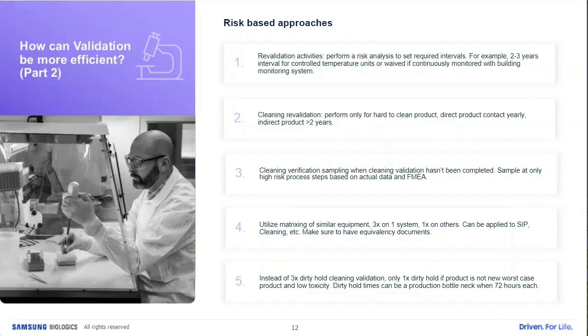The other thing is risk-based matrixing. I've hit on multiple large facilities where you have the same type of equipment. If you have 10 or 15,000 liter bioreactors, why do SIP validations, sterilizing in place, 3 times on each one, when I can do maybe 3 on one and a single check on the other 9 vessels? That same approach can apply to equipment, SIP, cleaning, anything like that.